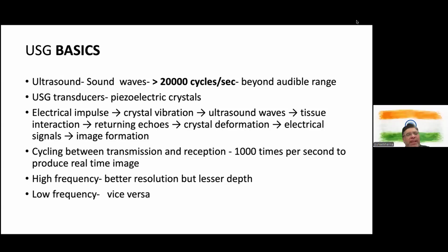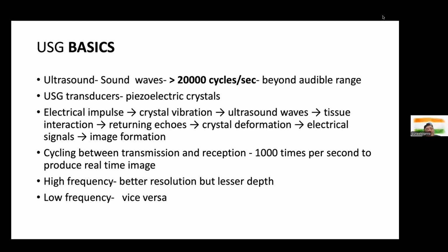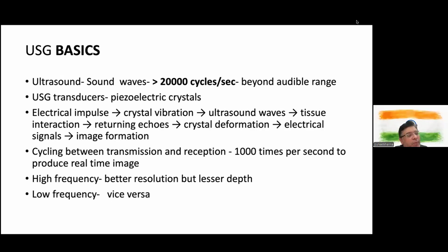So let's stick to the basics. Very clear: ultrasound, sound waves beyond the audible range, transducers, piezoelectric crystals. Now, what has changed in ultrasound transducers? Previously, we used to have 3, 4 different probes: a linear probe, low frequency probe, echo probe, curvilinear probe. Nowadays, what advancements have taken place? Piezoelectric used to be a collection of crystals. Now, with new technology, you have single crystal probes, and a single probe can change its configuration to a linear, to a curvilinear, to an echo probe. This is what is coming in the present day scenario.